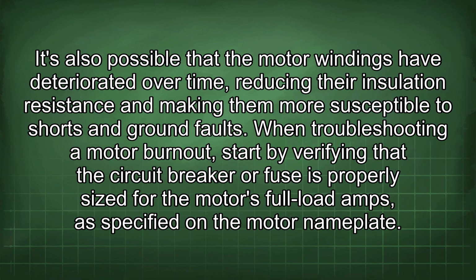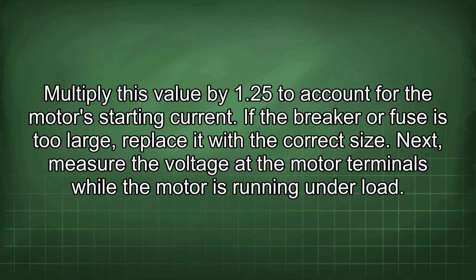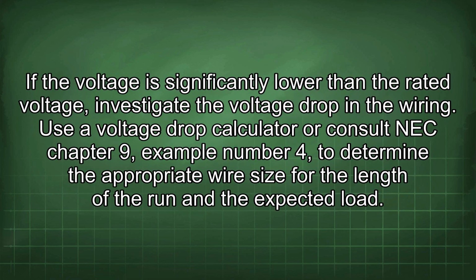When troubleshooting a motor burnout, start by verifying that the circuit breaker or fuse is properly sized for the motor's full load amps, as specified on the motor nameplate. Multiply this value by 1.25 to account for the motor's starting current. If the breaker or fuse is too large, replace it with the correct size. Next, measure the voltage at the motor terminals while the motor is running under load. If the voltage is significantly lower than the rated voltage, investigate the voltage drop in the wiring.